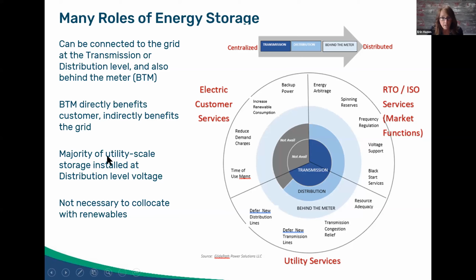We're in the multi-megawatt size projects. I've developed, we've got 4 construction-ready projects in New York. They're all 20 megawatts, and they are 4 or 6 hour duration batteries. Those are typically installed at the distribution level voltage, the medium voltage. Typically your transformer costs are not as expensive as if you were trying to attach to the grid at a very high voltage, so a lot of our interconnections are in the 13,000 range voltage.